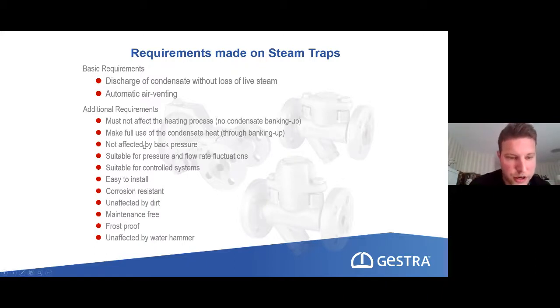What other things can we say? A steam trap should be suitable for pressure and flow rate fluctuations. For instance, if I start up the system, we have a lot of cold surfaces all around. It's the pipelines which are cold, it's the heat exchanger vessel which is cold. So in the very beginning, we will have a lot of condensation. The steam will condense on each and every surface, and the amount of condensate is quite high. But after a while, when everything is heated up sufficiently, the amount of condensate will drop down.